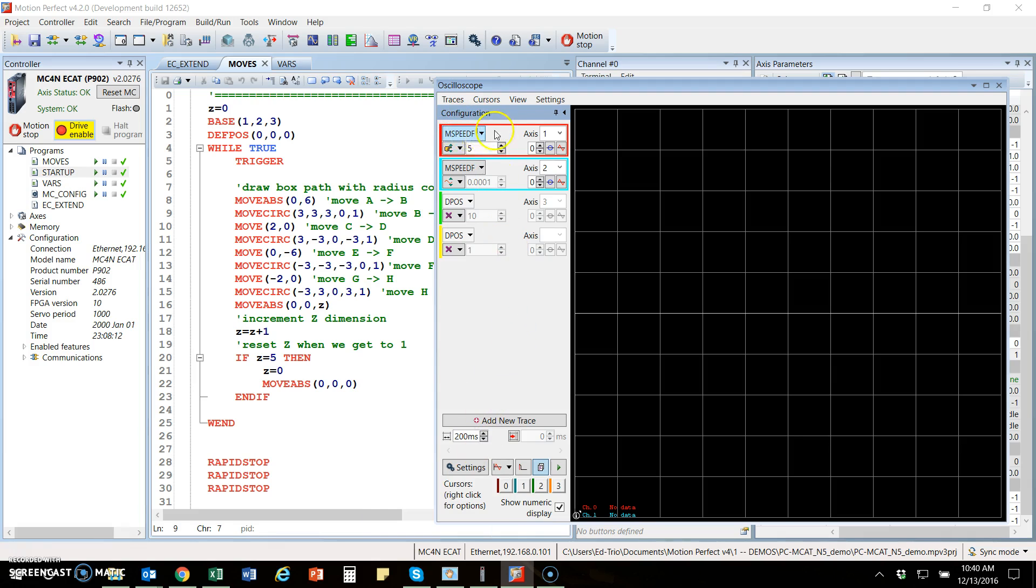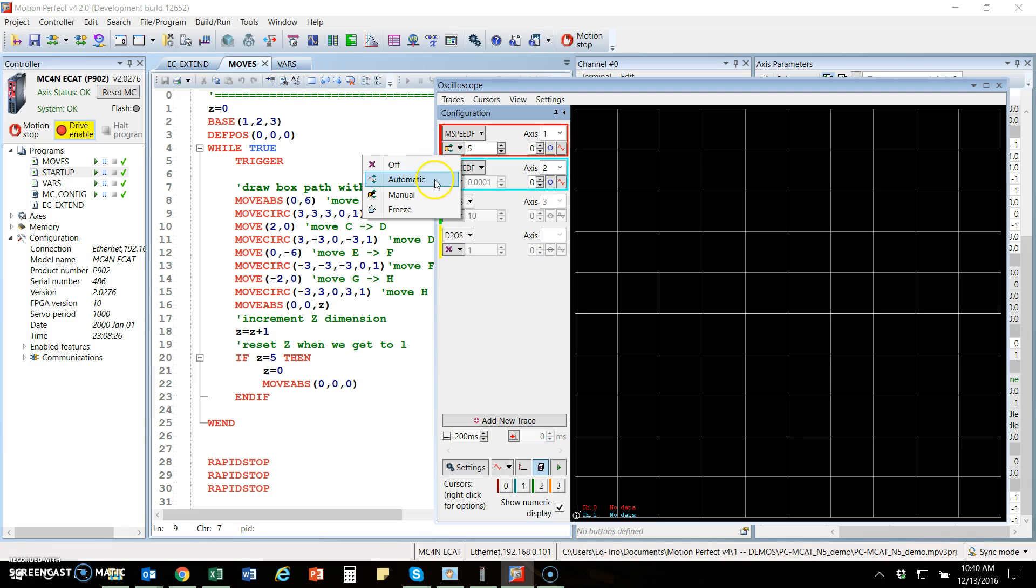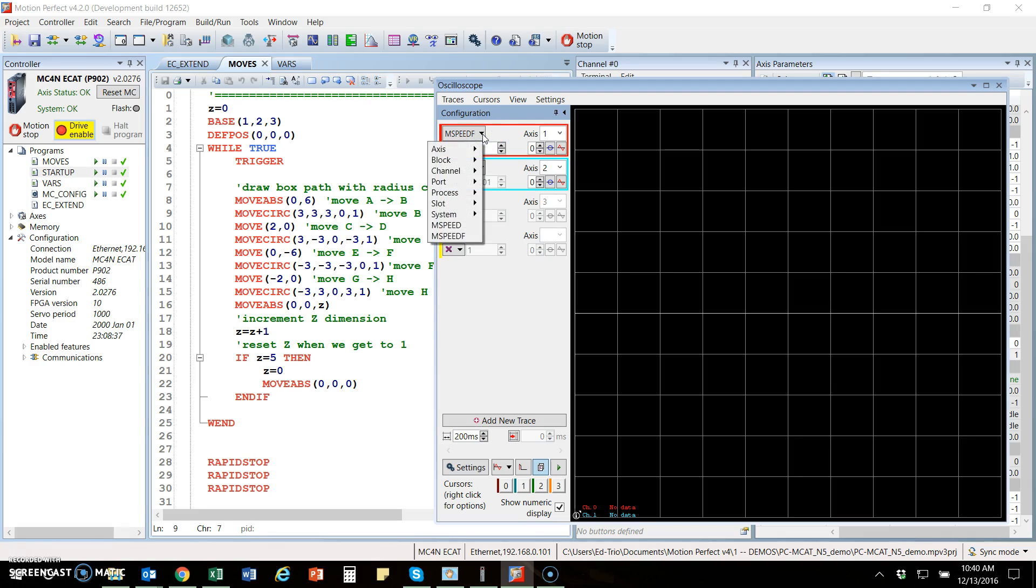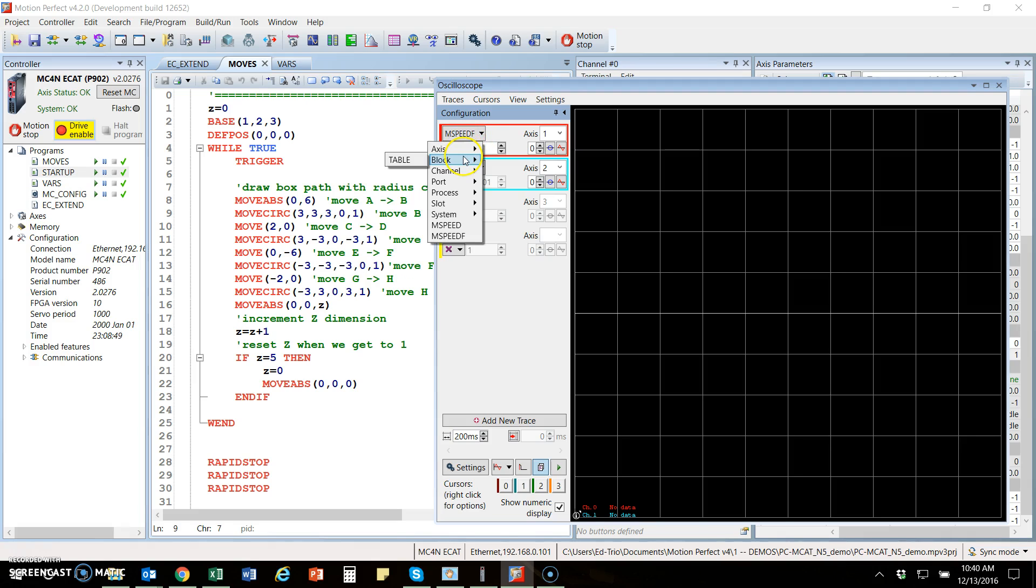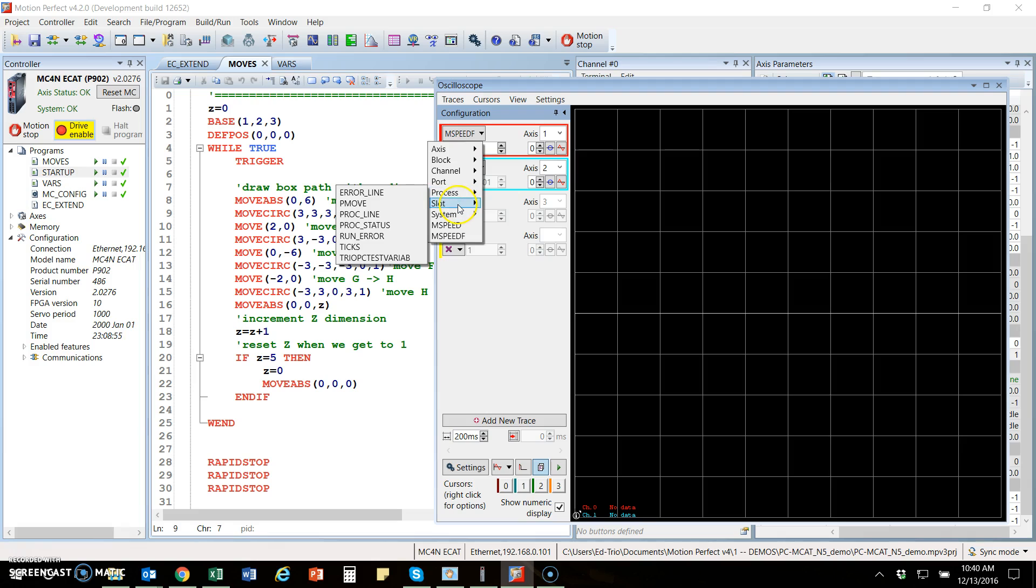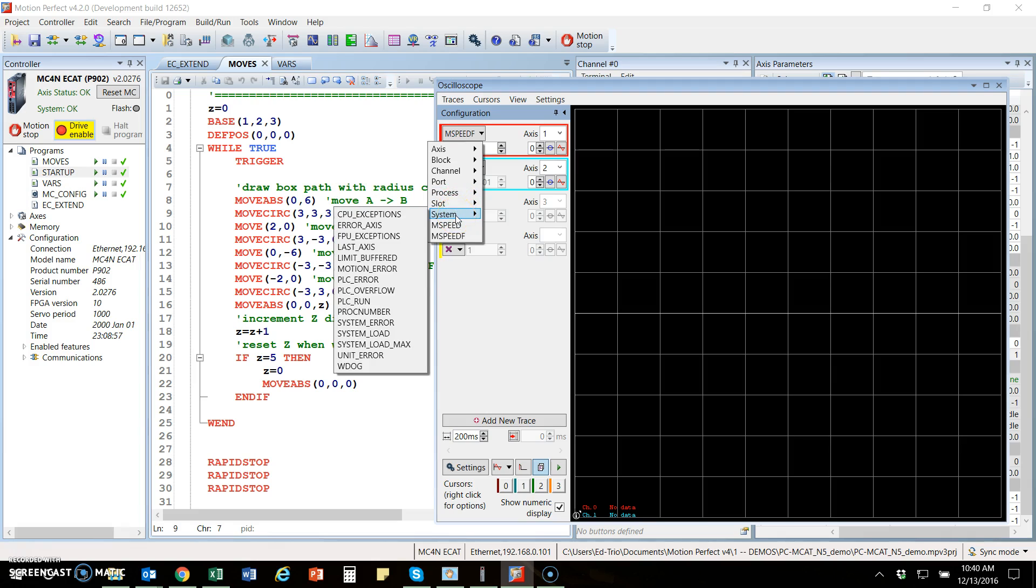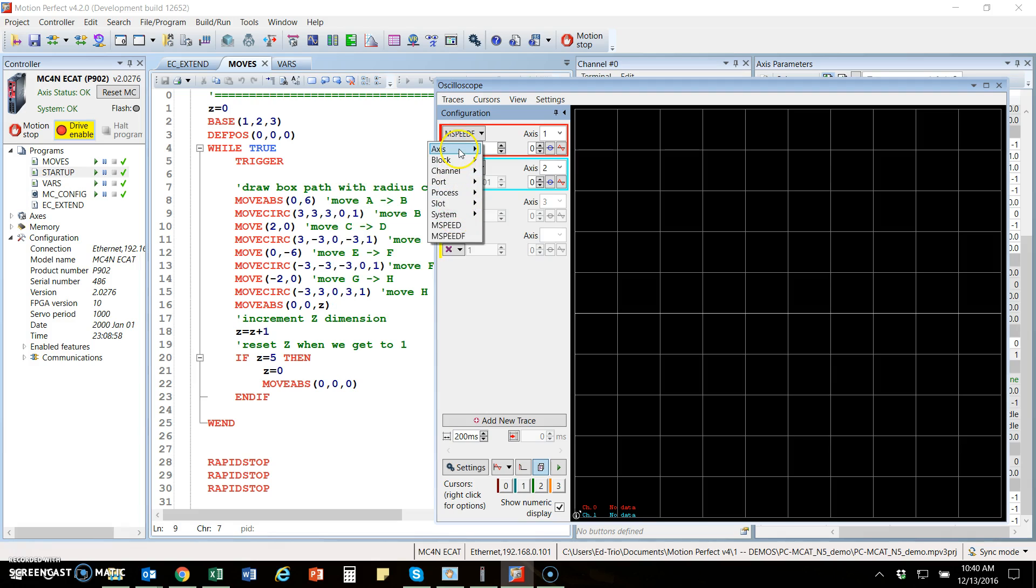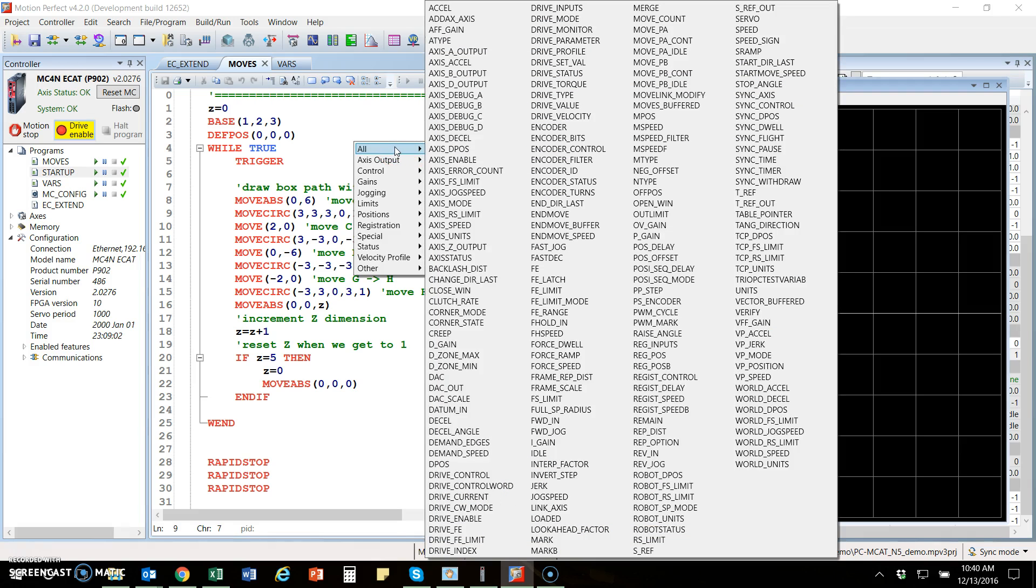Let's go through the tools here real quick. By default, you have four channels. You can add additional channels by clicking this button here. You can enable and disable the channels. Typically automatic is good enough. Then you pick the signal that you want to look at. You can find those by going through these groups here, such as inputs, process data, system data. Typically it's axis. You can look at all of the axis parameters, so there's quite a bit to look at.